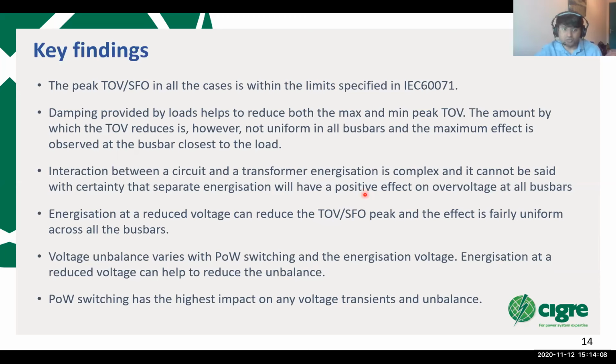And the amount by which the TOV reduces is found to be not uniform across the network, and the maximum impact will be at the bus bar which is closest to the demand. The interaction between a circuit and a transformer energization is a complex phenomenon, and it cannot be said with certainty that the energization of the transformer separately will always have a positive impact, or will have a positive impact equally or at all the bus bars.